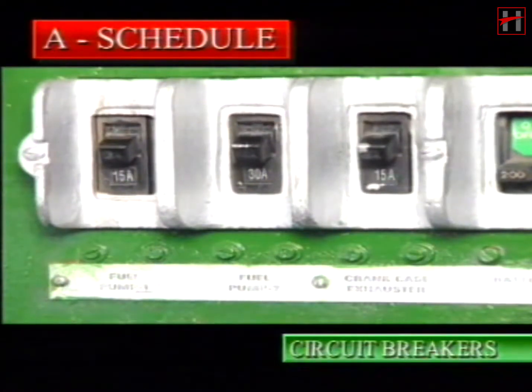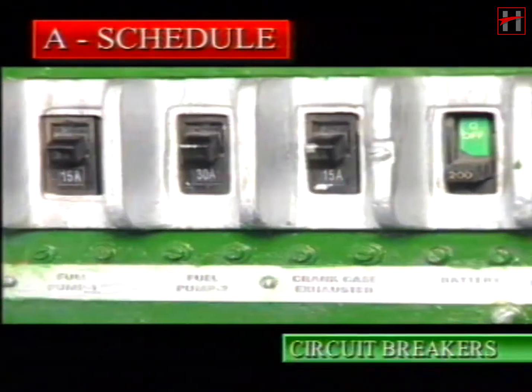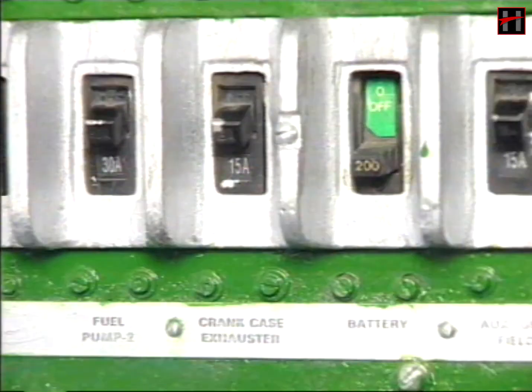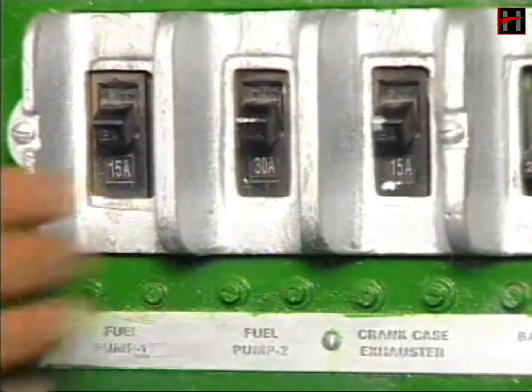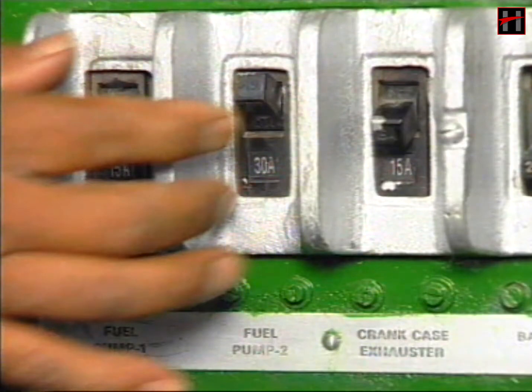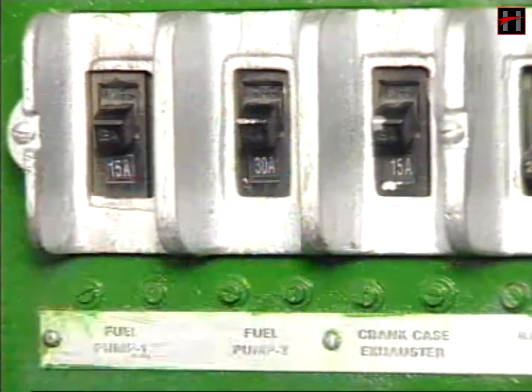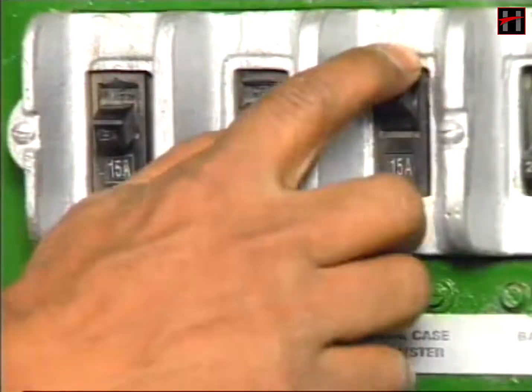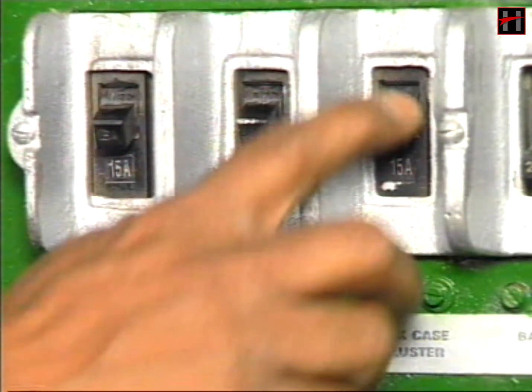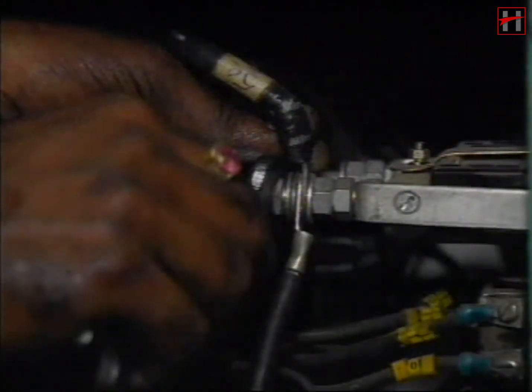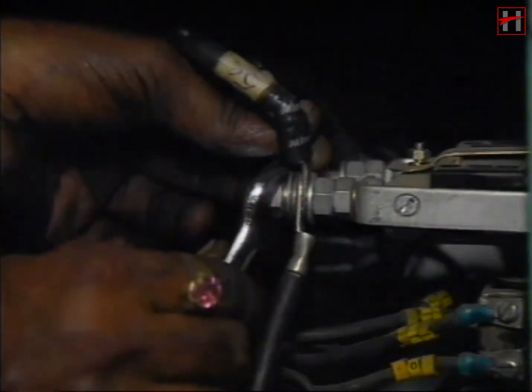In the A schedule of circuit breakers, visually check the foundation screws of all the circuit breakers. Check the operation of the circuit breakers manually. They should work properly on their positions. Check the terminal connections of the circuit breakers. All connections must be fully tightened.